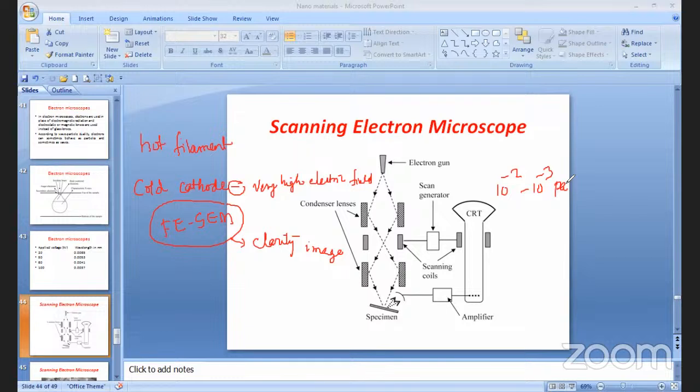Okay. So this makes electron microscopes. However, some manufacturers have been successful in marketing the electron microscopes known as environmental microscopes. In these, the samples can be at high pressure, around a few hundred pascals, like 100 to 500 pascals.